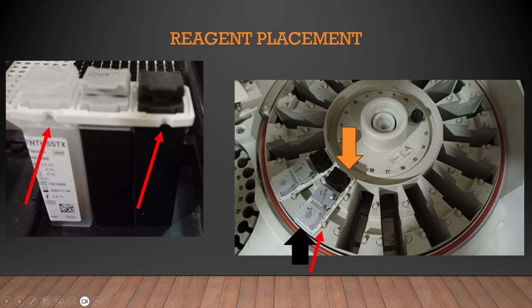Okay, and once you keep the reagent down, then only loosen the cap. And when you are taking the reagent out, first fasten all the caps and then only remove. Make it a habit. Many times I have seen that with one hand they hold the reagent and then loosen all the caps and try to put it, and the reagent falls off, the reagent liquid will come out. Okay, that type of mistake should never be made. It is not a very good practice.